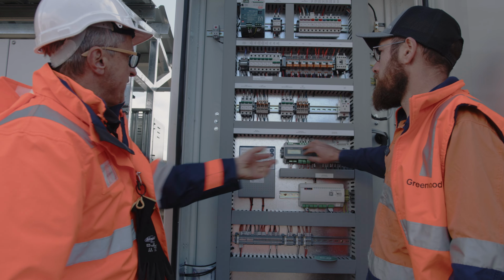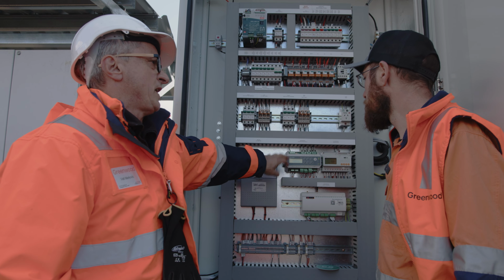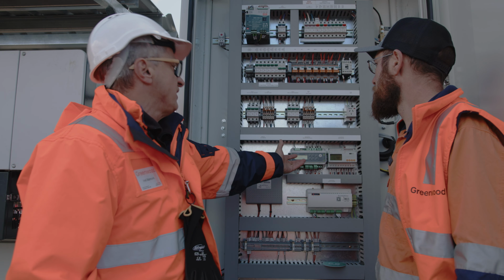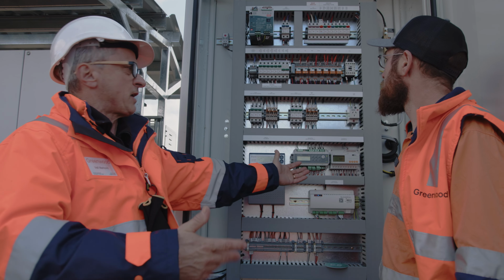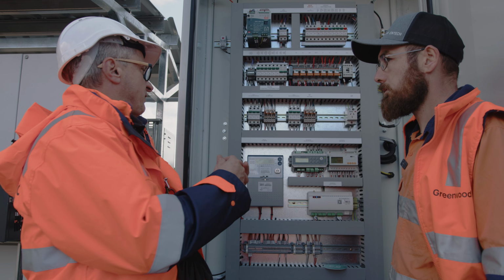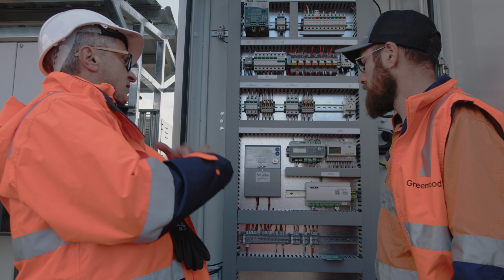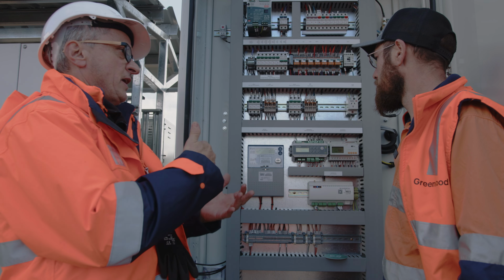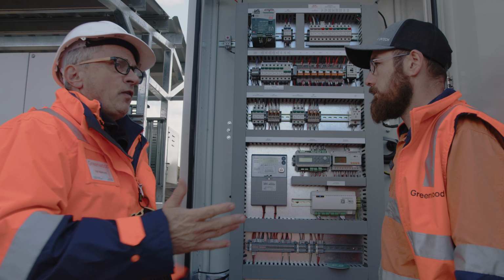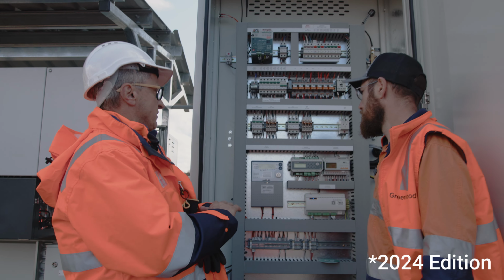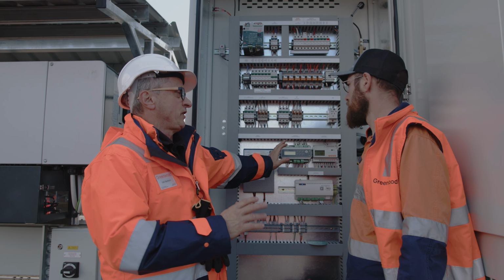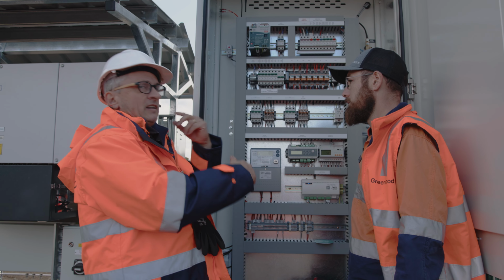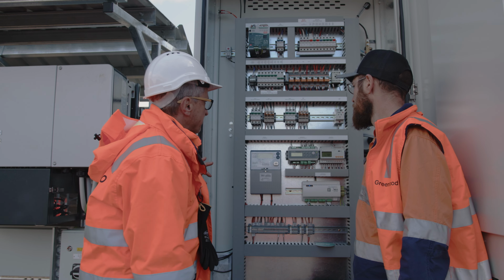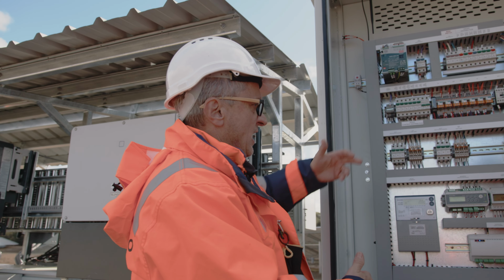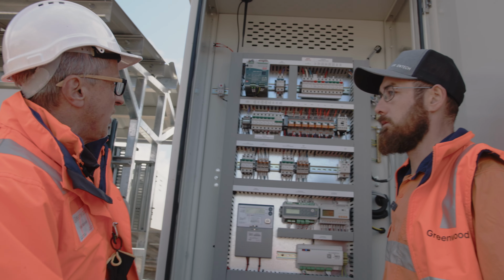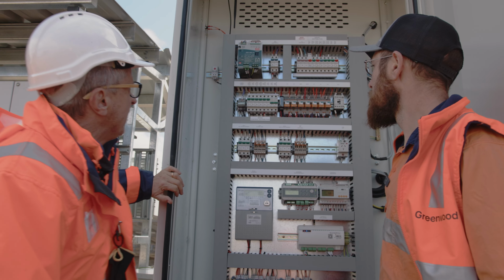Yep. So this is the brains. This is the relay, and it used to be called secondary protection because it effectively replicates the primary protection within inverters, but it's Plan B. Since the 4777.1 2024 edition, we don't call this secondary protection, we call it interface protection. You've got the main switchboard behind and you've got the transformer on that side. And we're just going through the components here.